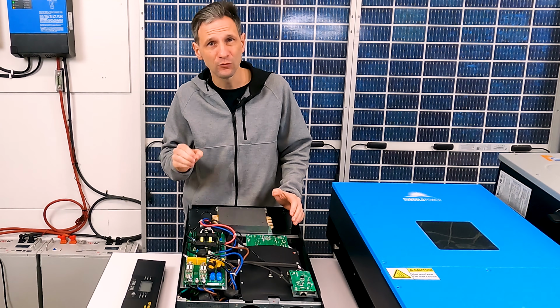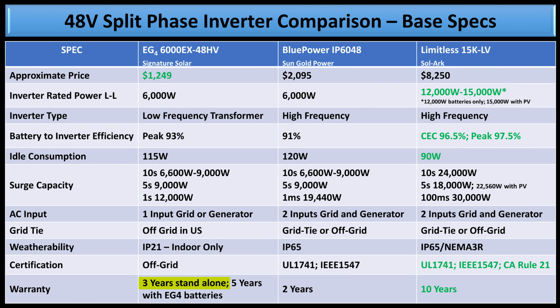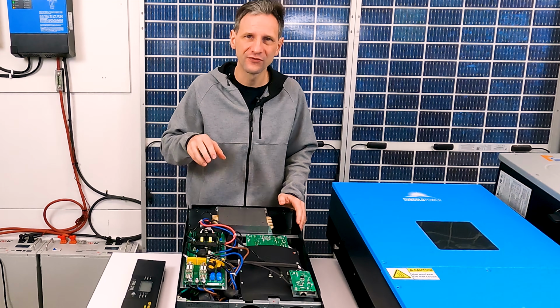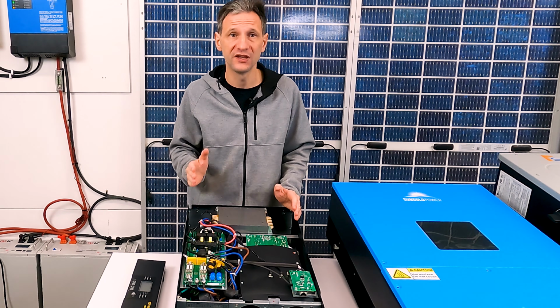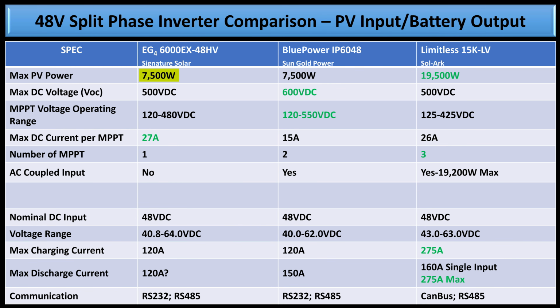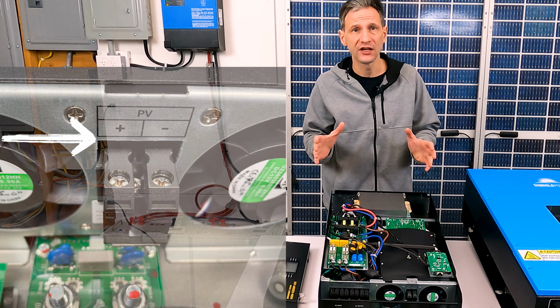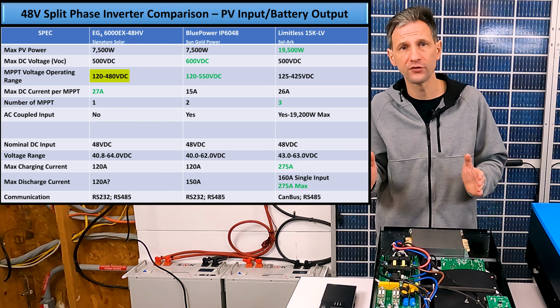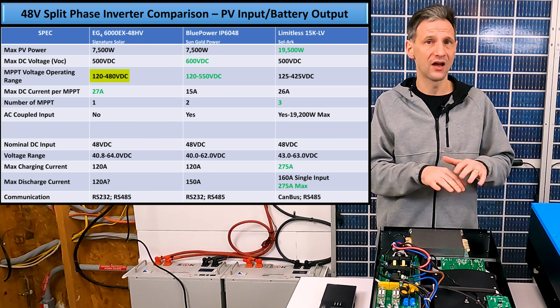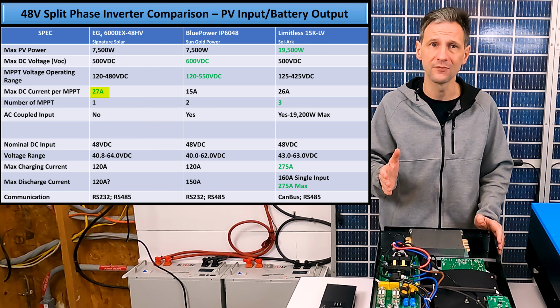This inverter has a decent warranty of 3 years, but if you pair it with EG4 batteries, which are also a great value solution, it increases the warranty to 5 years. As an all-in-one solution, even this budget-friendly version has very capable PV input. The max PV input is 7,500 watts, and it comes with a very respectable 500 volt maximum input. It has only one MPPT, but the tracking range is 120 volts to 480 volts, and the max current is the highest of all three units at 27 amps.